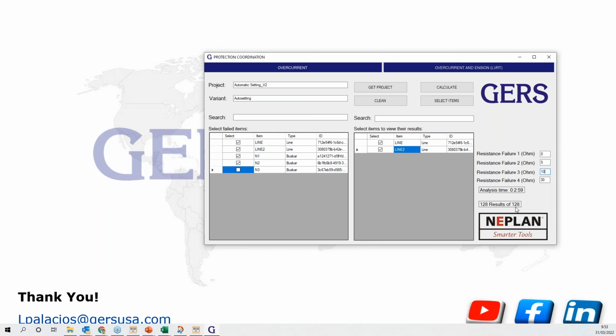In the small system it was 128. And for each simulation, we are getting the short circuit levels. And for each short circuit level, we can validate the tripping time of the protection. So we have automated here different applications for that. But this is an external application just to illustrate the capabilities of the web services, because we know that, for example, NEPLAN allows to get the protection assessment that offers some visual indicators about the possibilities or the improper settings that we have in the network.